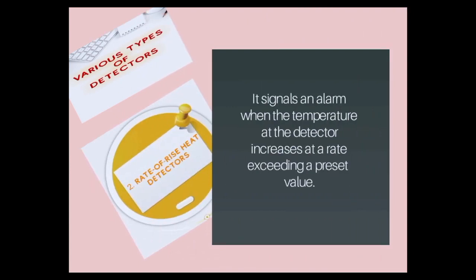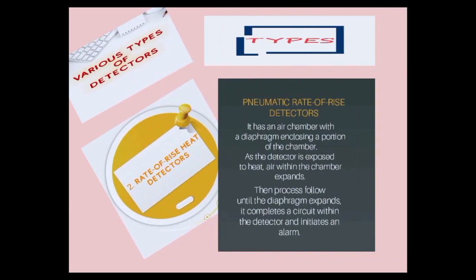It signals an alarm when the temperature at the detector increases at a rate exceeding a preset value. Types of rate of rise heat detectors. We have the pneumatic rate of rise detectors. It has an air chamber with a diaphragm enclosing a portion of the chamber. As the detector is exposed to heat, air within the chamber expands until the diaphragm expands. It completes the circuit within the detector and initiates an alarm.